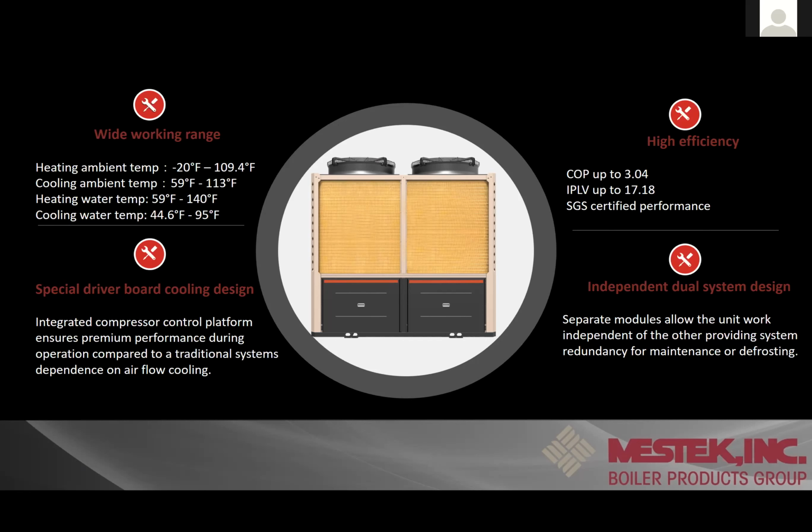Over on the high efficiency side of it, we have a COP of 3.04. That's us rated at design temp that AHRI makes us do. And then you have your IPLV, which is the integrated part load value. That's basically because it's an inverter, they're taking it as it modulates and then coming up with an efficiency value there. So that's a pretty nice thing to look at. And then separate modules will allow a unit to work independent of the others, providing system redundancy and maintenance, like we talked about, even on defrost. So I'll show you that in the next couple of slides.